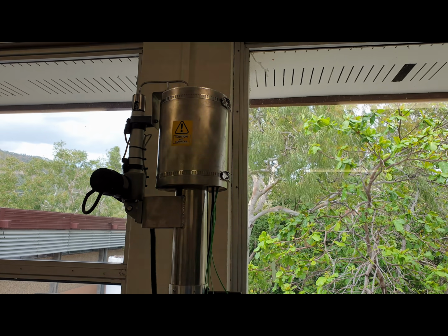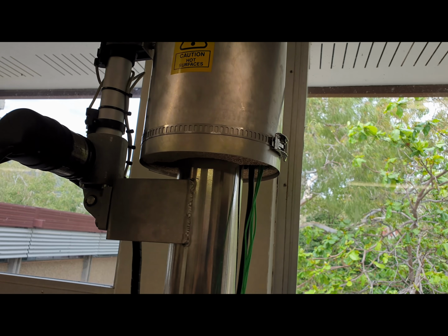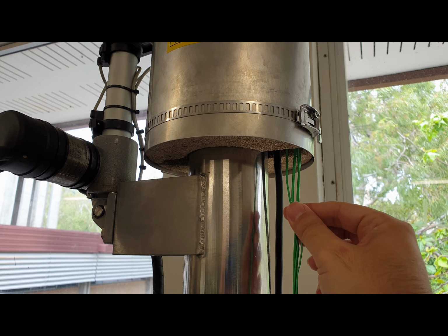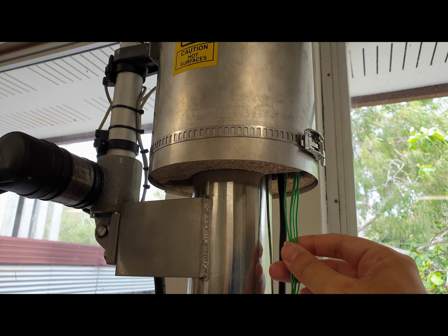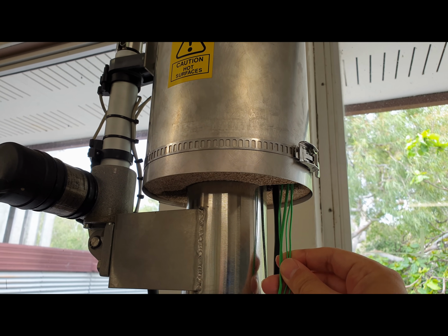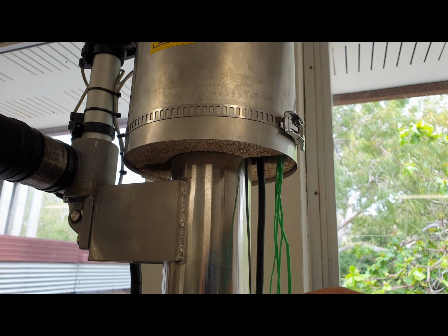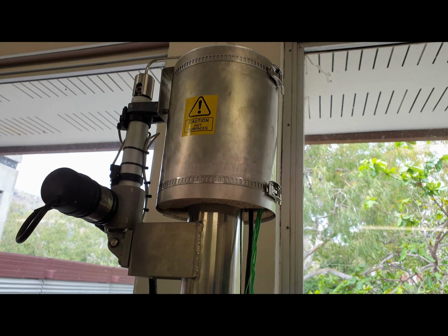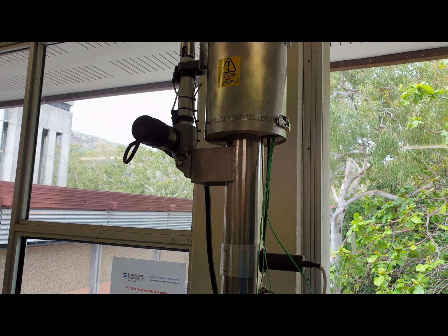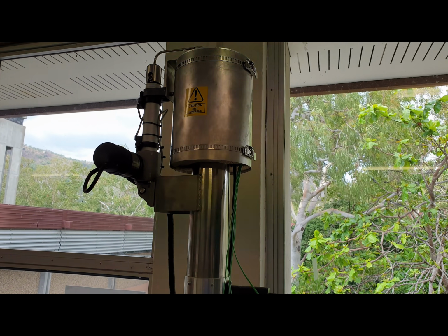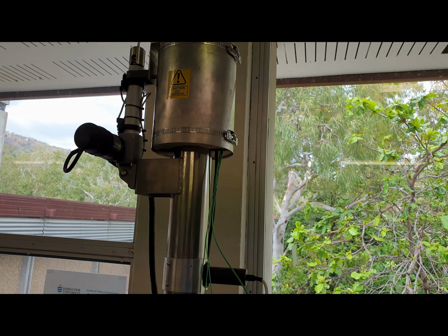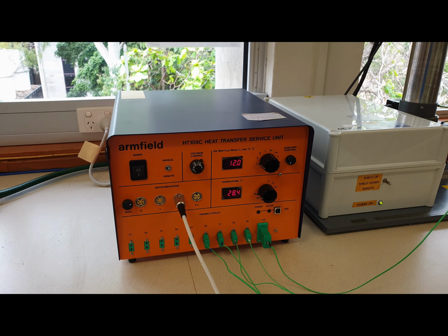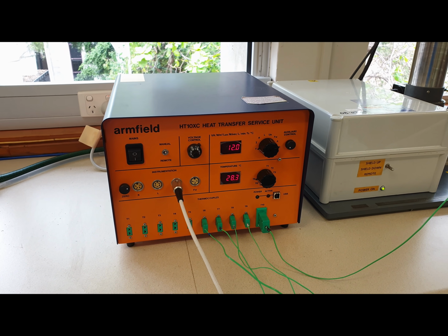we had 3 different thermometers or thermocouples inside the heating section. As you can see, we have 4 cables here for T7, T8 and T9, and one more, which you can see is a bit thicker, is for T10, which is the temperature of the hot surface. That is a bit thicker because the temperature of the hot surface is much higher, and we need a bit thicker wire.